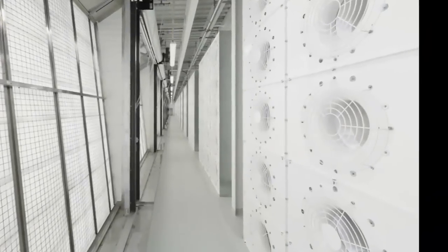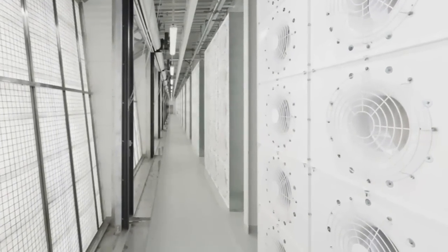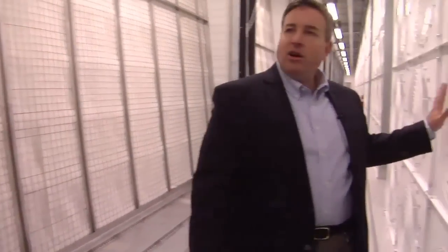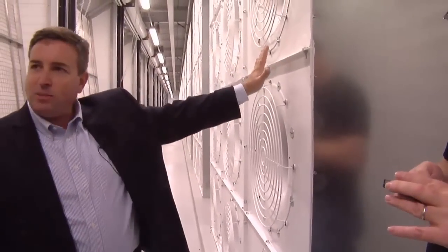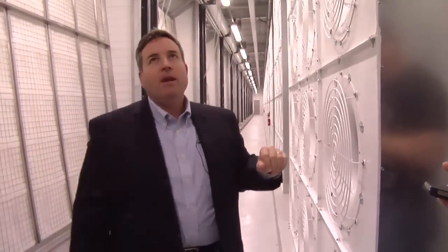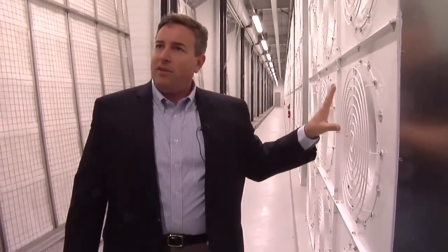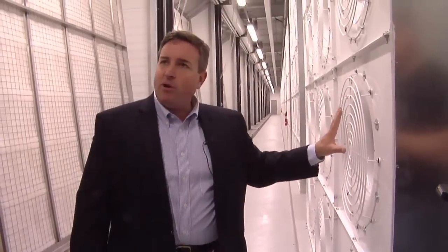So the mist eliminator on my right side here, you can feel there's no moisture carryover, just cool, somewhat moist air. The fans here are drawing that air through the system and pushing it into the next space, which then directs it down into the space below. These, what we call fan walls, have very, very highly efficient fans in them. They have small, like 5 horsepower motors.